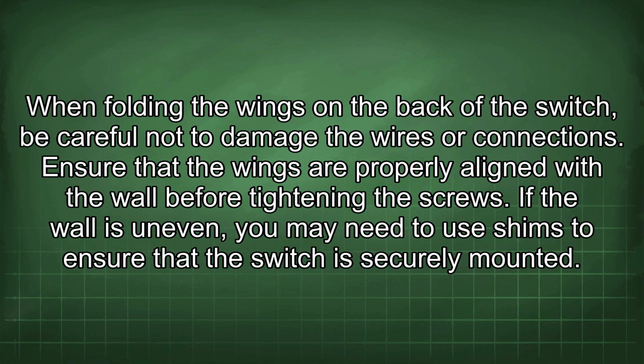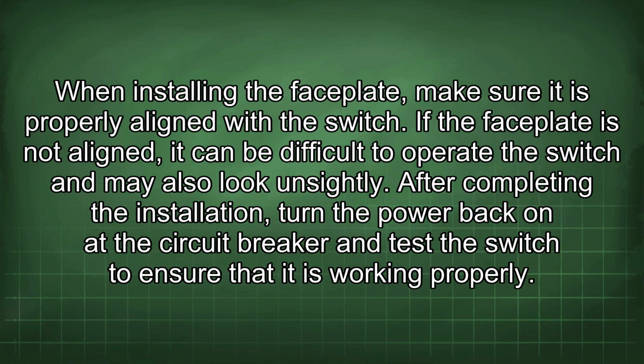When folding the wings on the back of the switch, be careful not to damage the wires or connections. Ensure that the wings are properly aligned with the wall before tightening the screws. If the wall is uneven, you may need to use shims to ensure that the switch is securely mounted. When installing the faceplate, make sure it is properly aligned with the switch. If the faceplate is not aligned, it can be difficult to operate the switch and may also look unsightly.